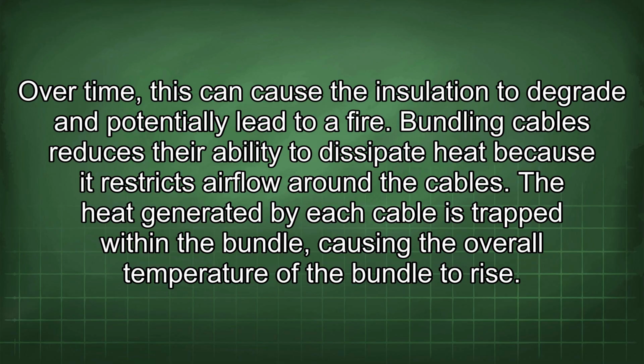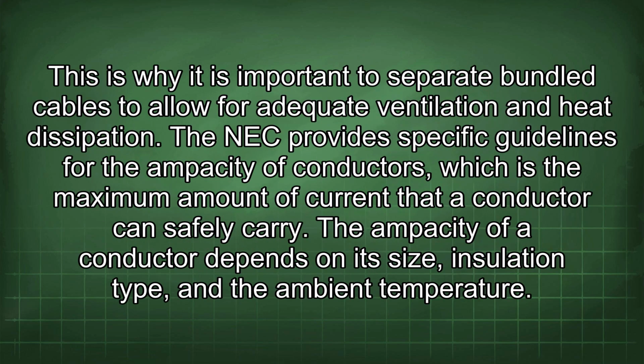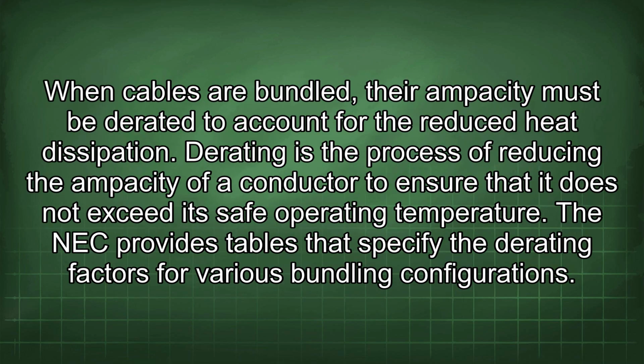Bundling cables reduces their ability to dissipate heat because it restricts airflow around the cables. The heat generated by each cable is trapped within the bundle, causing the overall temperature of the bundle to rise. This is why it is important to separate bundled cables to allow for adequate ventilation and heat dissipation. The NEC provides specific guidelines for the ampacity of conductors, which is the maximum amount of current that a conductor can safely carry. The ampacity of a conductor depends on its size, insulation type, and the ambient temperature. When cables are bundled, their ampacity must be derated to account for the reduced heat dissipation.